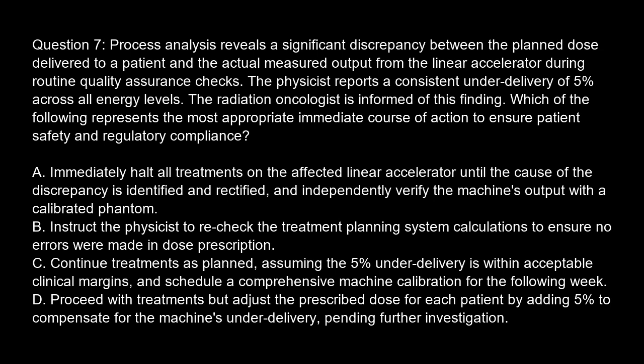Option A. Immediately halt all treatments on the affected linear accelerator until the cause of the discrepancy is identified and rectified, and independently verify the machine's output with a calibrated phantom. Option B. Instruct the physicist to recheck the treatment planning system calculations to ensure no errors were made in dose prescription. Option C. Continue treatments as planned, assuming the 5% underdelivery is within acceptable clinical margins, and schedule a comprehensive machine calibration for the following week. Option D. Proceed with treatments but adjust the prescribed dose for each patient by adding 5% to compensate for the machine's underdelivery, pending further investigation.